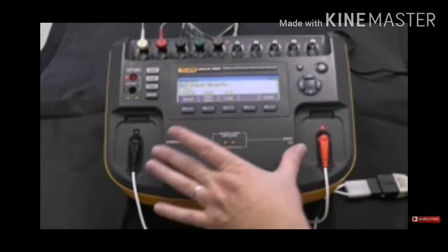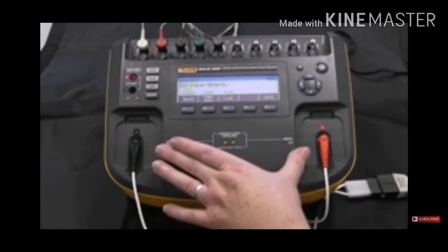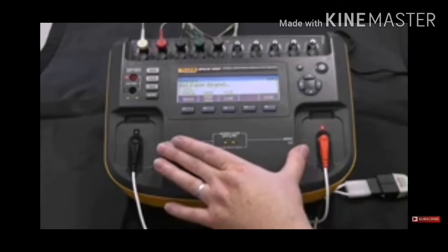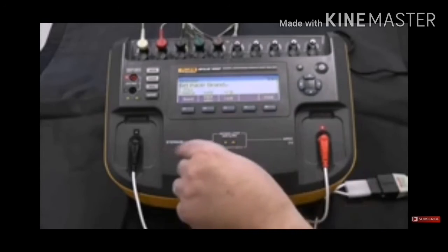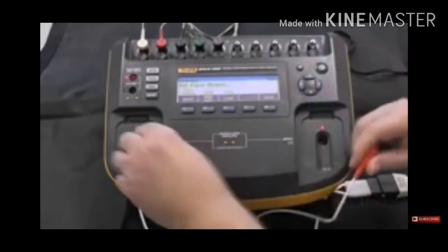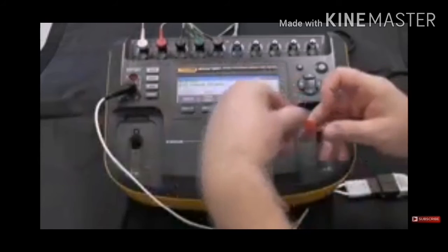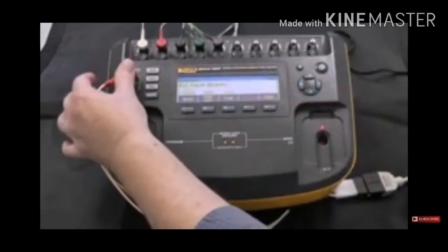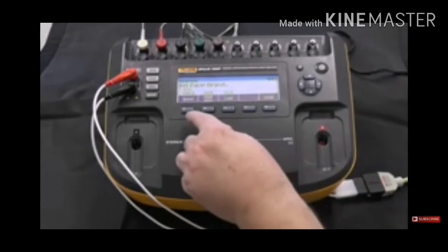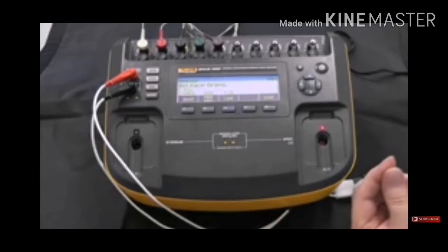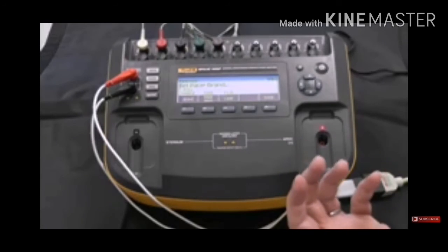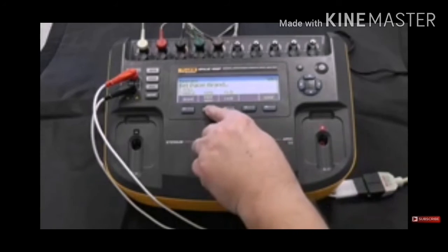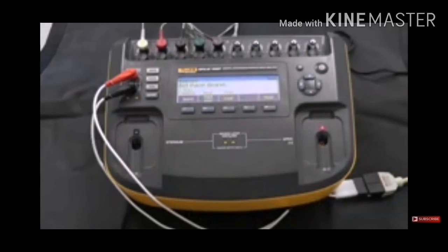Now, if we just leave it on the defib energy inputs here, the problem with that is that 50 ohms is not necessarily the appropriate load for every brand and model. So the best way to do this is to move our connections from the 50 ohm load and connect them over here on the pacer inputs. And now when we've selected the brand, we have already selected internally to the Impulse 7000 the load appropriate for that brand. We want to also tell the Impulse 7000 that we're using the pacer posts, and then we want to pick done. Now we're ready to receive energy from the pacemaker, as you can see that we're doing right here.